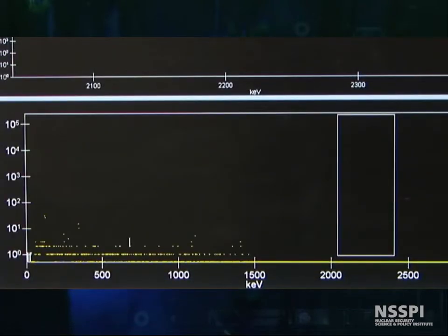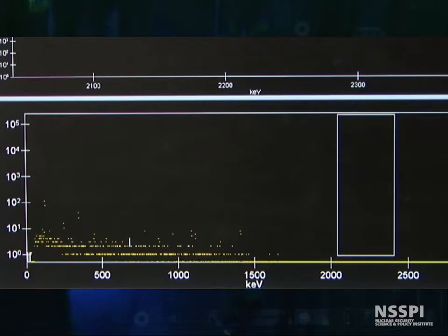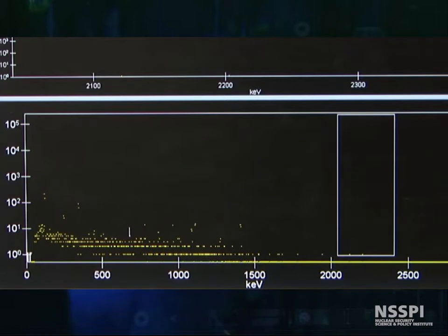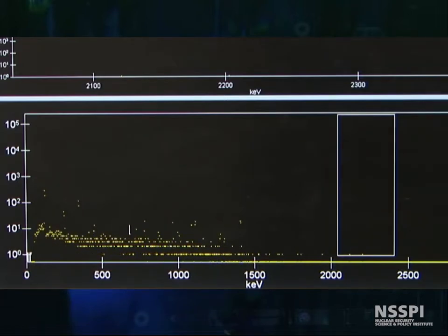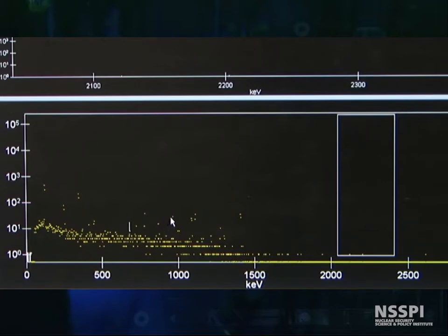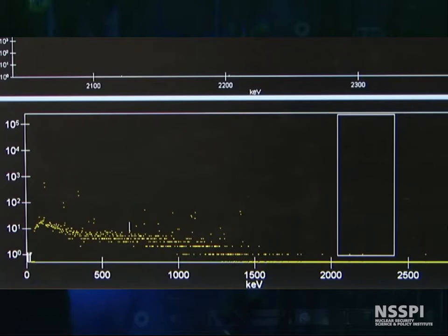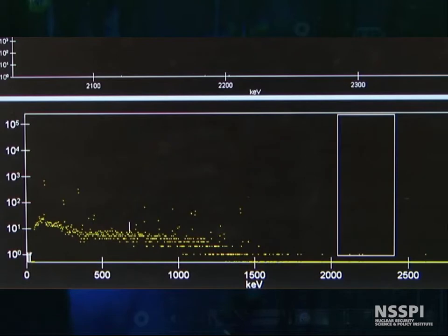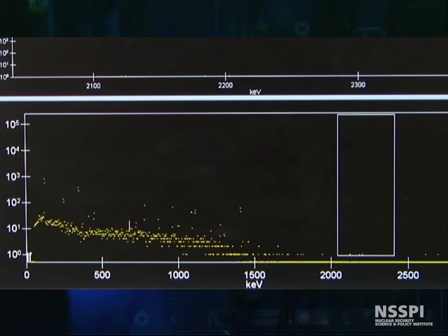Let's watch this. And here you can see — oh my gosh, there's a dozen peaks here. We know the yields very well, and it's built into the library. We're going to let this count for a minute, and then we're going to use the software as part of our counting system to construct the absolute efficiency curve for us. Now we feed this data to the software, and voila — here is our absolute efficiency curve.